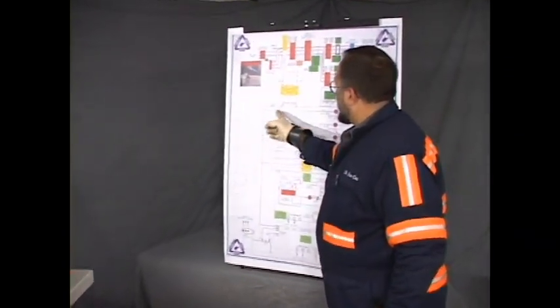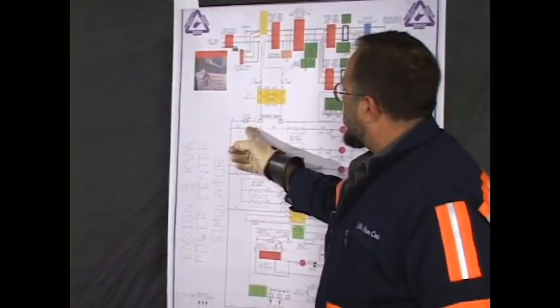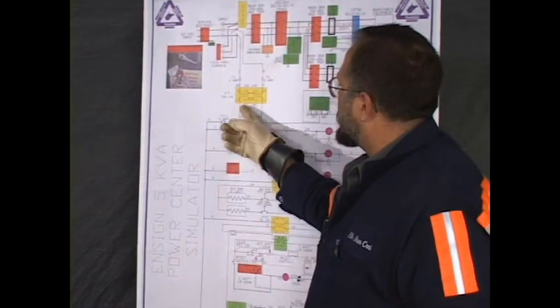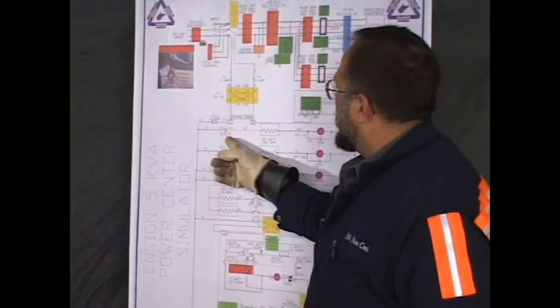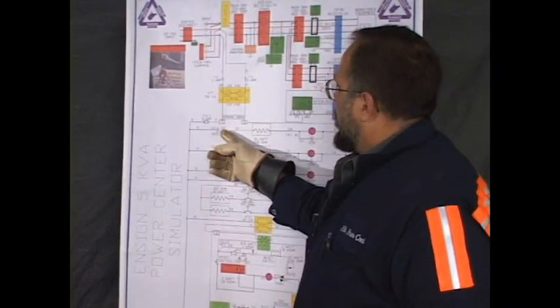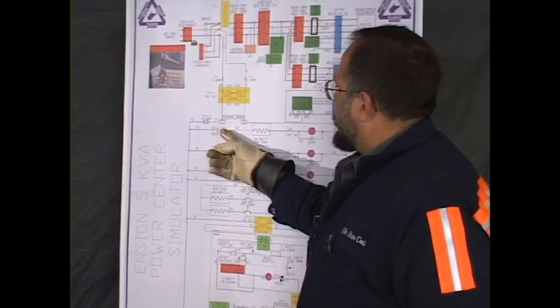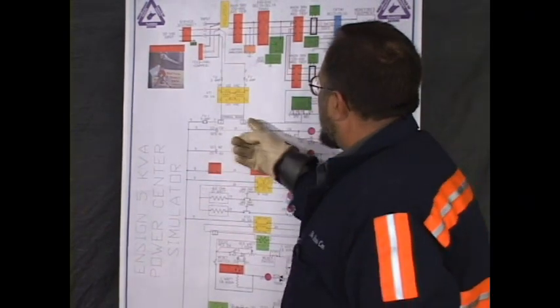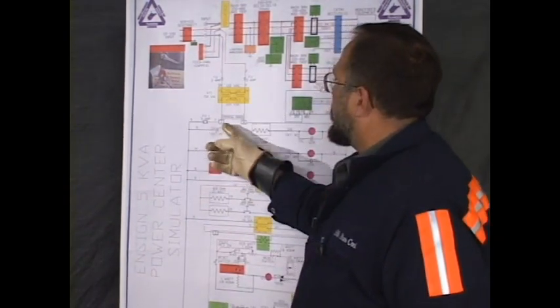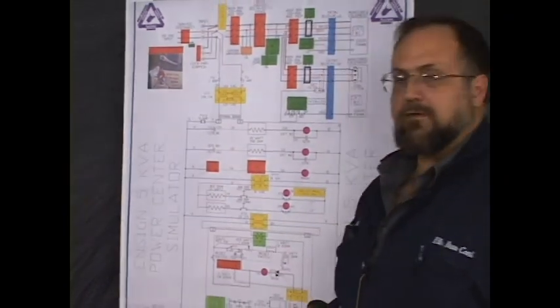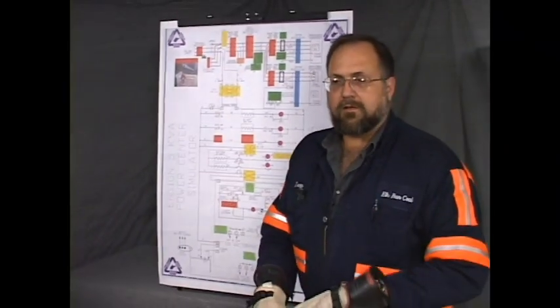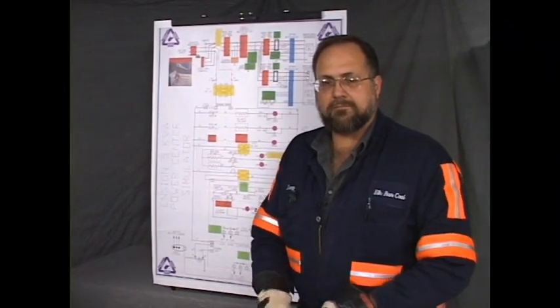where one probe on terminal 1, wire 9, is reading to this side of the transformer. One probe on terminal 3 is reading to the other side of the transformer, and then there's an open contact between, with 120 volts. I would say you had a bad relay.